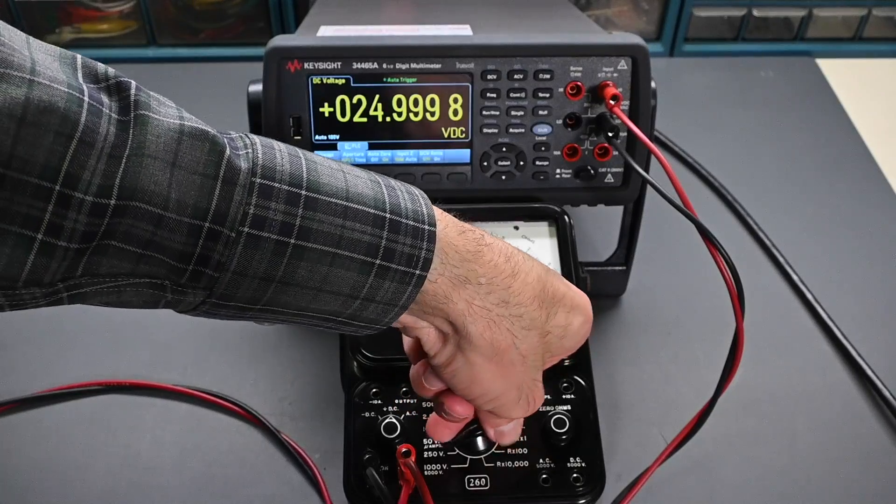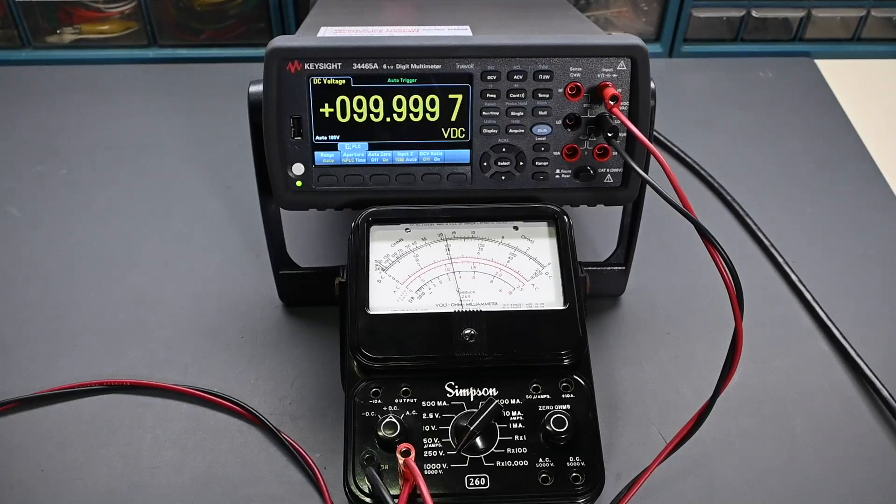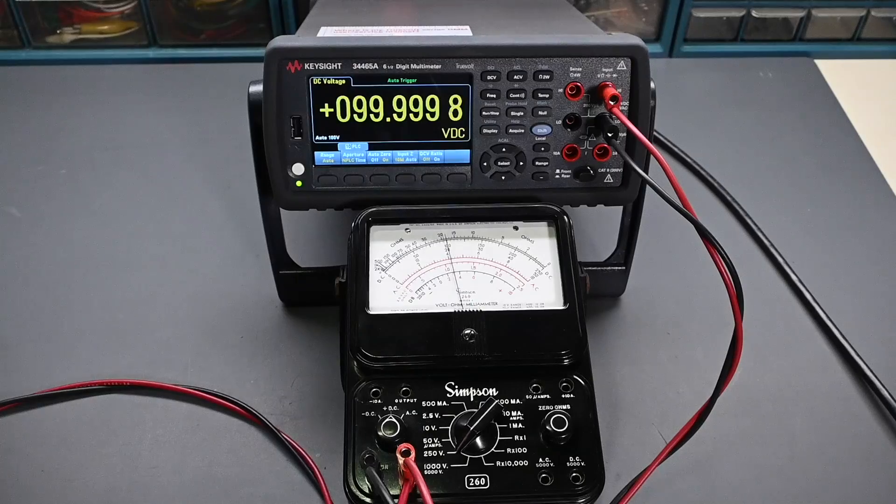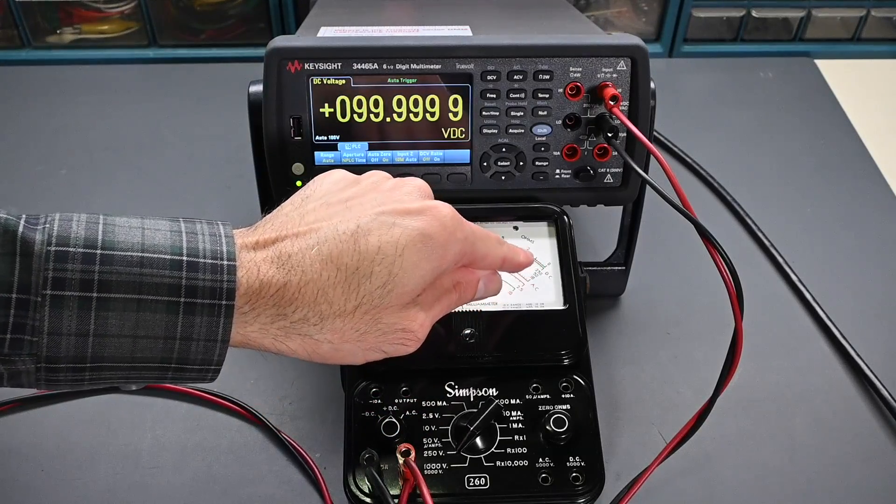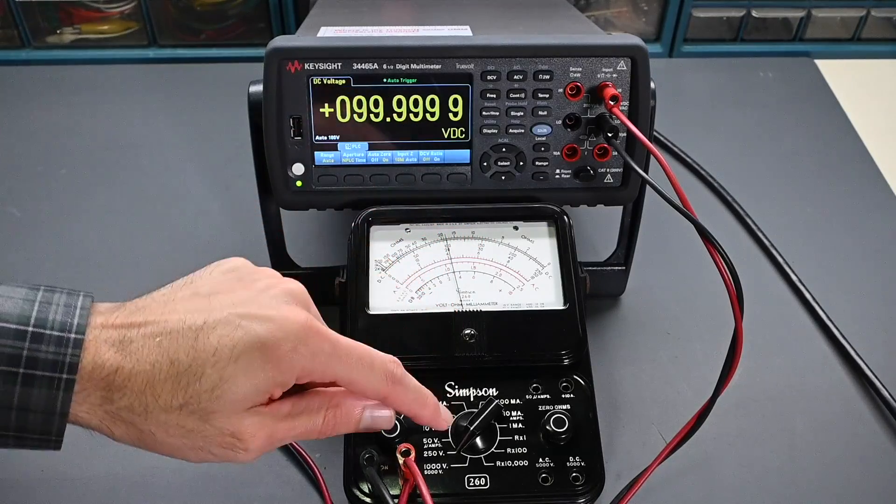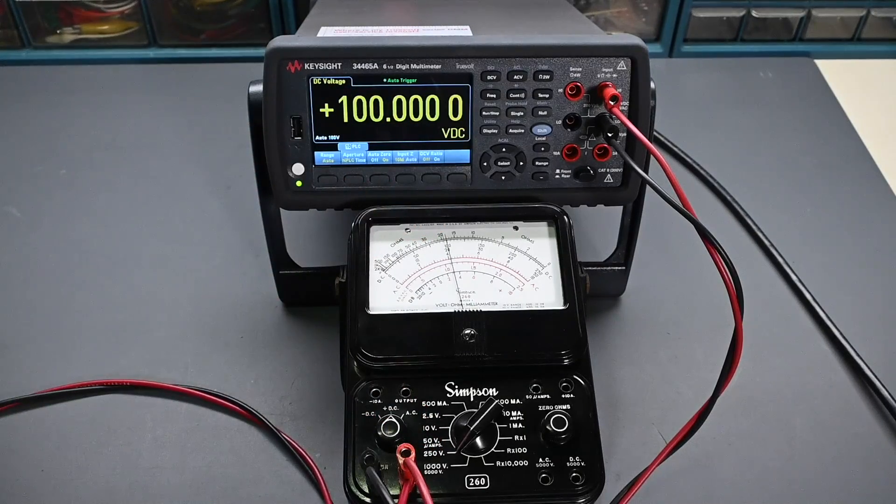Let's try 250 volts. So, for 250 volts, my power supply stops at 100 volts. So, we'll just go to that maximum. Alright, so there's 100 volts. 99, all 9's right there. And, that looks really good. So, 250 full scale. 200, 150, and 100. So, it's right on. Again, this is where the multiplier resistor was just repaired. So, that range has come back into the accuracy that we'd want to see. That looks perfect.